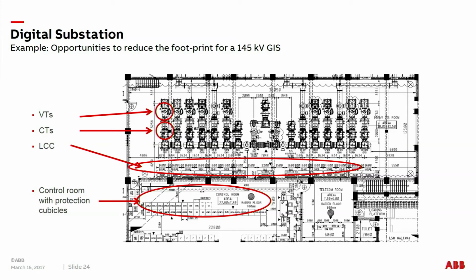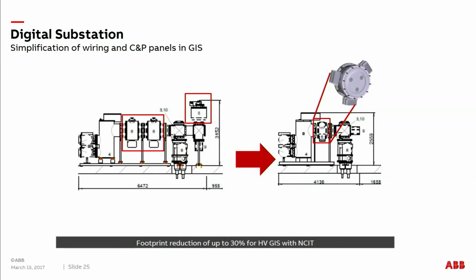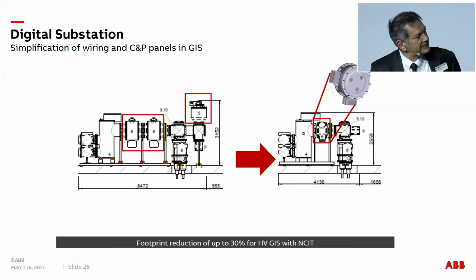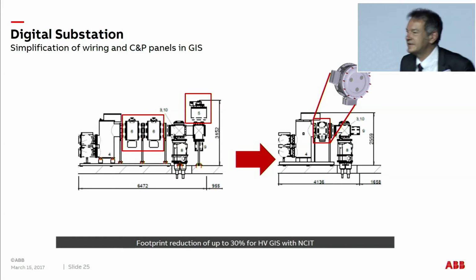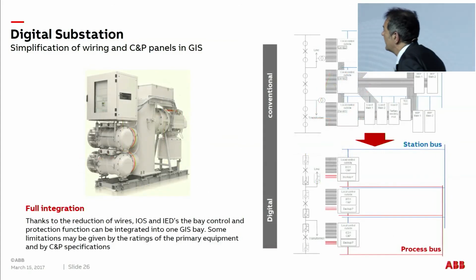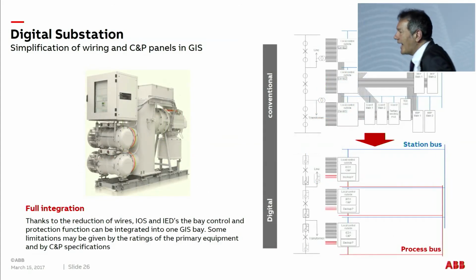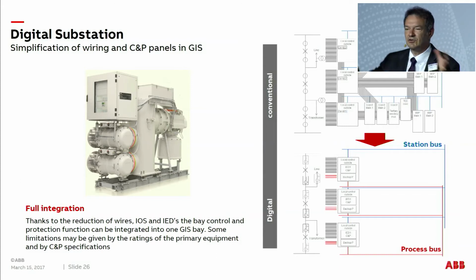You will see that all these electronics can be integrated into the primary equipment. So for a conventional GIS here, with current and voltage measurement, you will replace the measurement by sensors, and you see how much less space you will need in the future. The equipment even looks nice. Look, you get rid of all the cabling. This is conventional, this is now modern. And you can integrate control and protection very closely to the primary equipment.